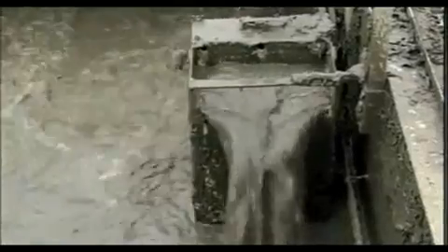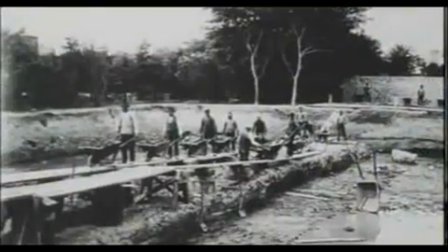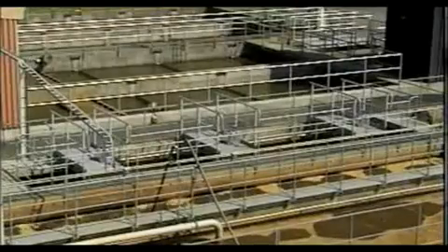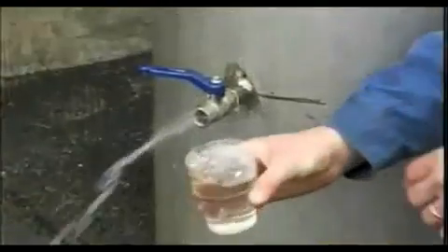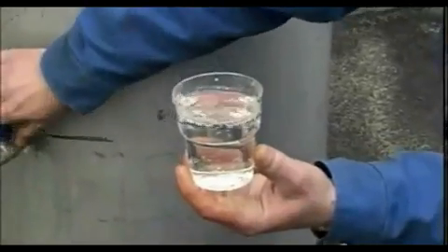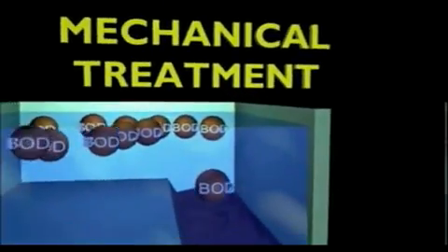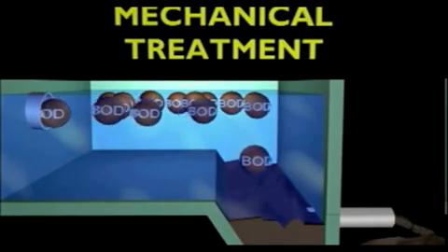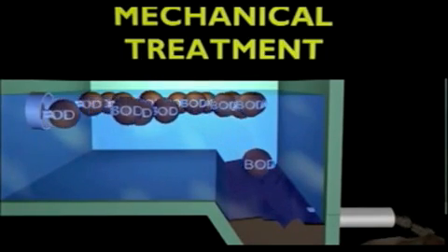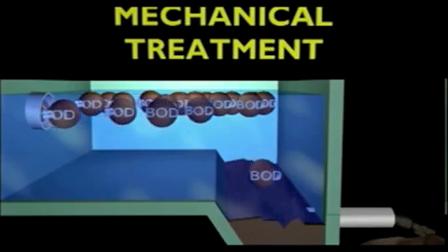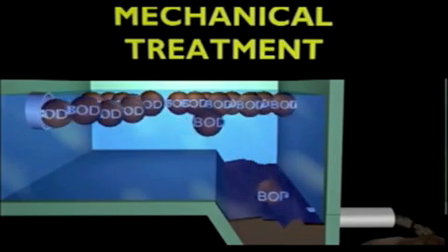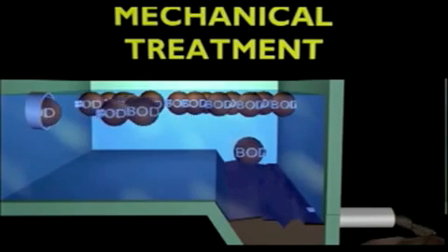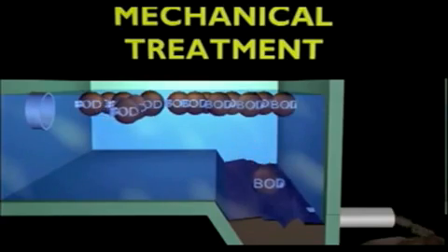The pollution can be removed by different methods, and a number of processes have evolved over the years. Today we apply reliable techniques to achieve the desired result. Mechanical treatment plants use sedimentation to separate particles. This is a simple process where large particles sink to the bottom and form sludge. Since only 1/3 of the organics will be removed by this process, biological or chemical purification is supplemented in order to meet increased requirements.